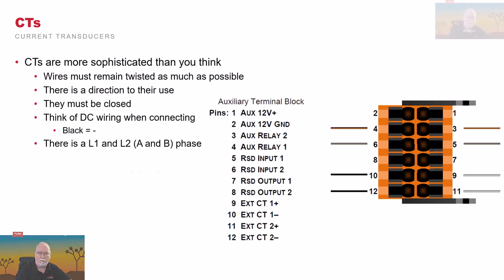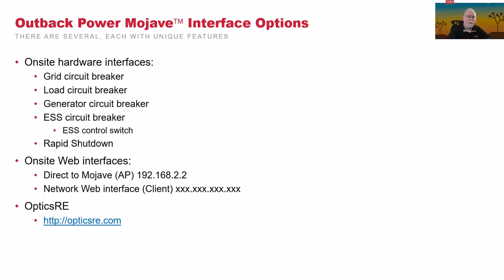Next, let's take a look at the Mojave power interface options. There are hardware interface options on the unit. This would be the circuit breakers: the grid breaker, the load breaker, the generator breaker, the ESS breaker. So these are all the on-site hardware controls. There's also an on-site web interface available through a Wi-Fi device. That'd be 192.168.2.2. And then once it's hooked into your network, you'll be able to reach it from anywhere within your local network using the IP address it's assigned. Finally, it will be talking to OpticsRE and will be sending information northbound.